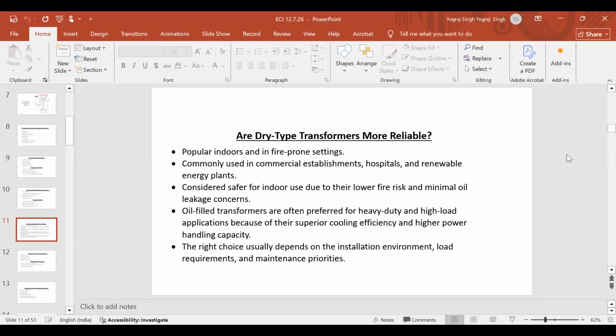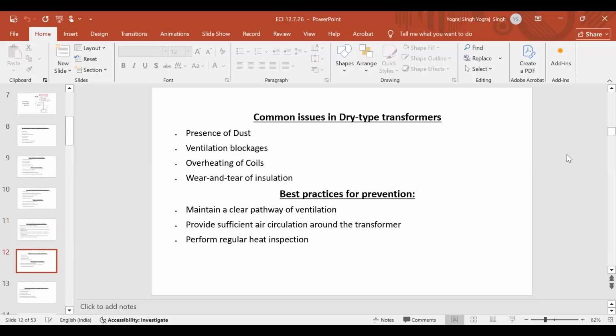What are the common issues with dry type transformers? Presence of dust, ventilation blockages, overheating of coil, wear and tear of insulation. If there is dust in your underground area, dust will settle on these. That will capture moisture. So these things reduce the insulating capability of the transformer.